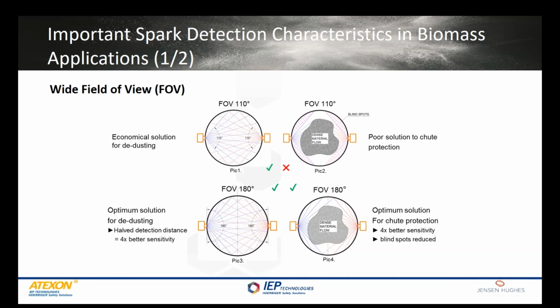Picture 3 shows that a spark detector which has a 180-degree viewing angle needs to measure only half the distance, because the other detector takes care of the other half. And this leads to 4 times better sensitivity level because of the square law of radiation. And picture 4 shows how much better the 180-degree detector works in a biomass chute. Both detectors are needed to cover only half of the chute, and there is no need to see through thick material flow to cover blind spots of the opposite detector.